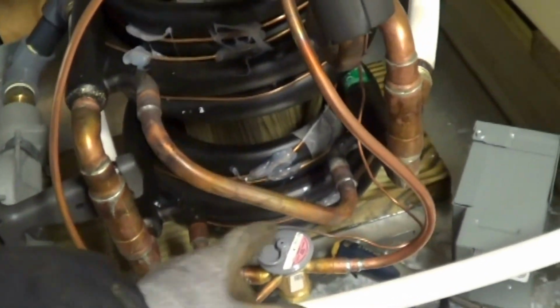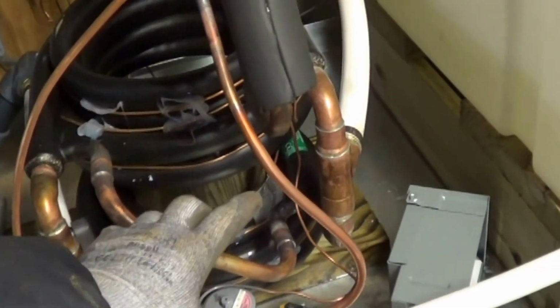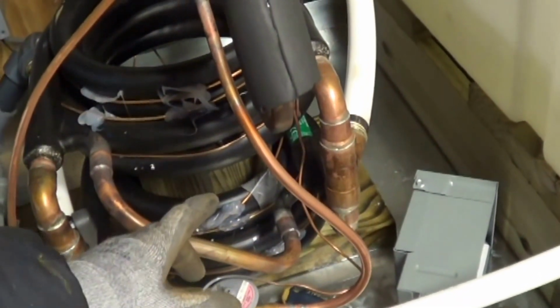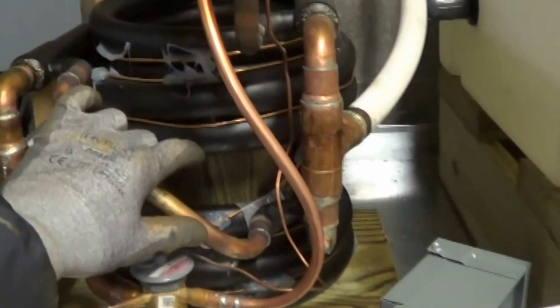I did find an issue here on the heat exchanger. The way I did it, I did parallel on the water and then series on the refrigerant, and you end up, the top heat exchanger is doing all the heating and the bottom heat exchanger is basically just holding liquid refrigerant, doing nothing. And you can see it on your temperatures. I'm getting 4.25 tons out of a 5-ton, and it's about 25 degrees outside.